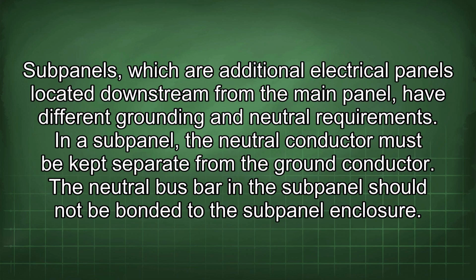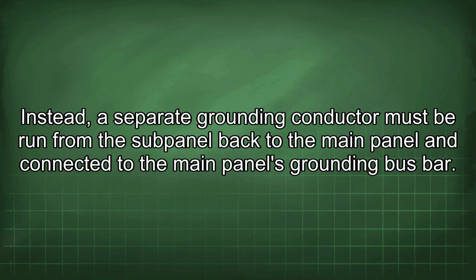Subpanels, which are additional electrical panels located downstream from the main panel, have different grounding and neutral requirements. In a subpanel, the neutral conductor must be kept separate from the ground conductor. The neutral bus bar in the subpanel should not be bonded to the subpanel enclosure. Instead, a separate grounding conductor must be run from the subpanel back to the main panel and connected to the main panel's grounding bus bar.